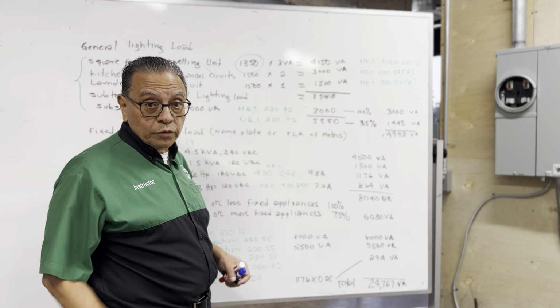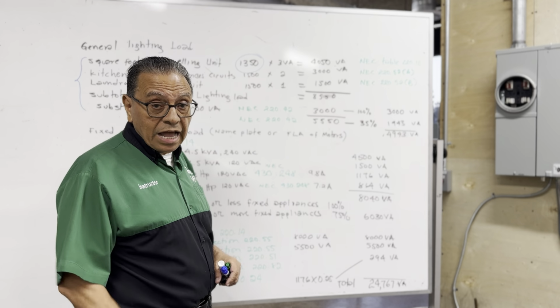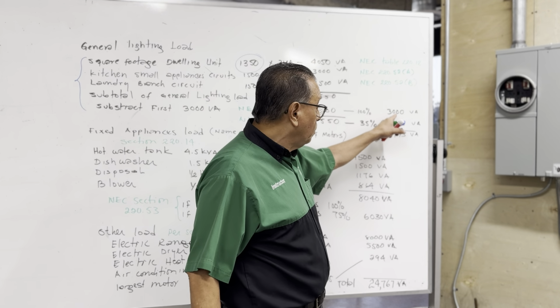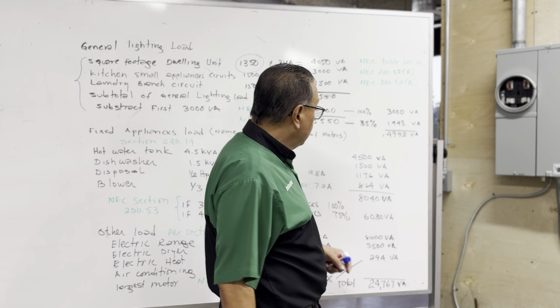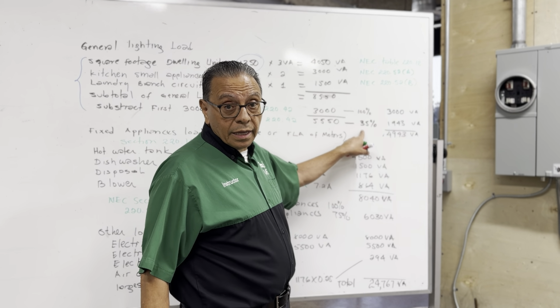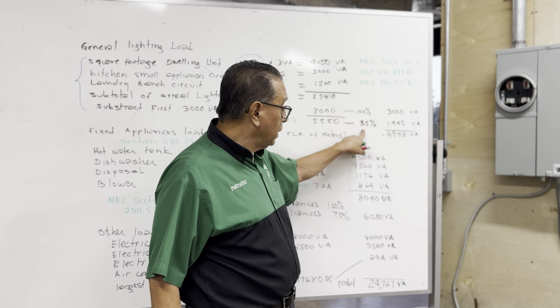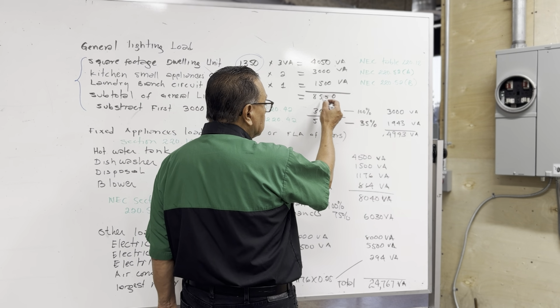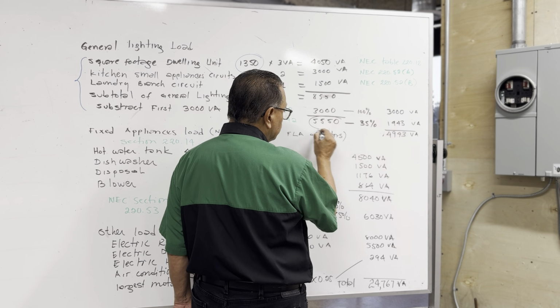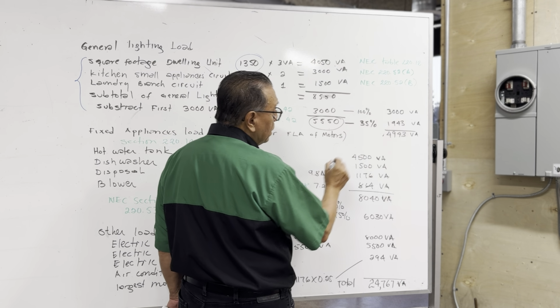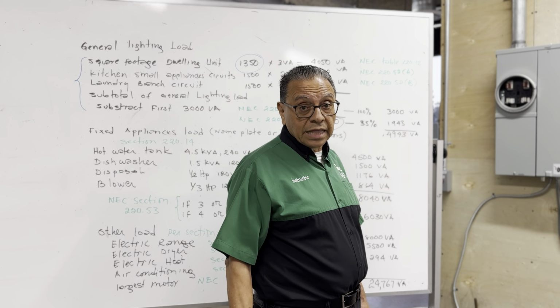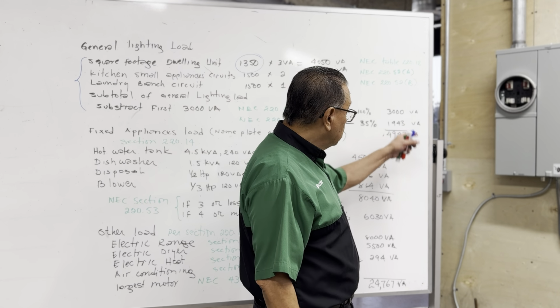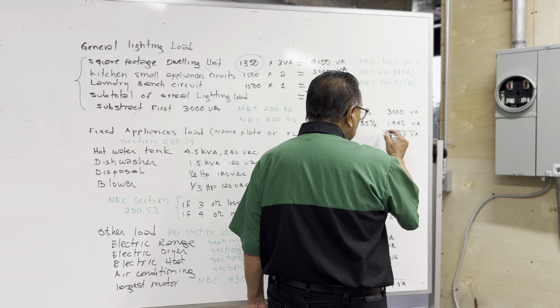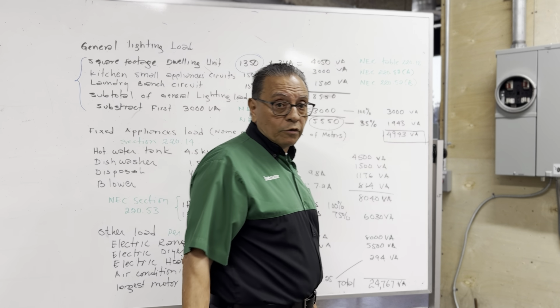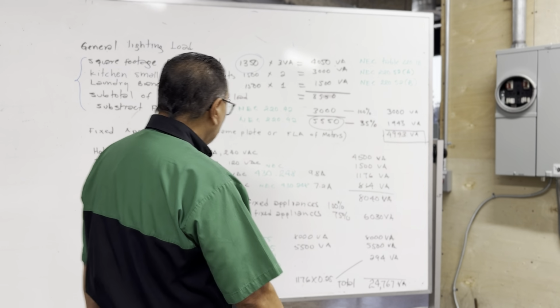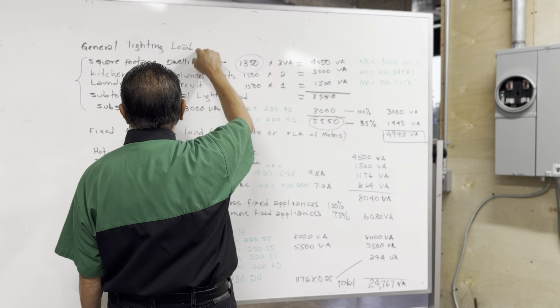Article 220.42 is asking me, from this total, the first 3,000, you will be asking the service company for the 100%, which is 3,000 volt ampere. The rest, you will be requesting the 35%, okay? So if I subtract 3,000 from 8,550, I get a total of 5,550. The first 3,000, I will be asking the service company for 3,000 volt ampere. For the rest, 35%, which is 1,943. If I add these two, I have a total of 4,943 volt ampere. This is what I need to be asking the service company for the general lighting load.